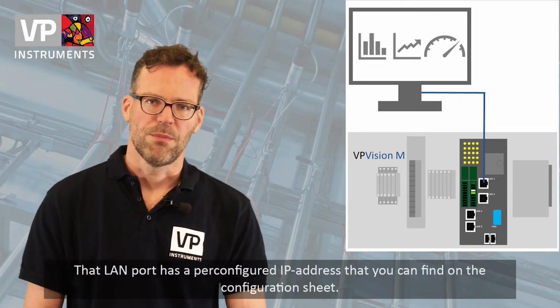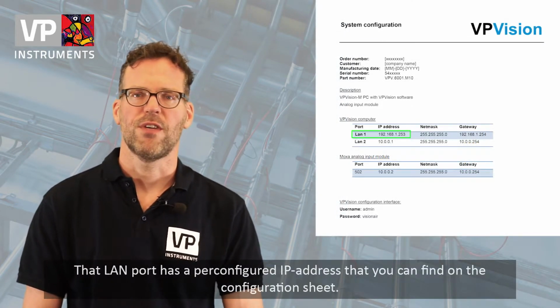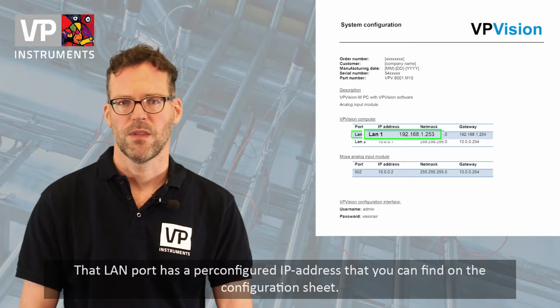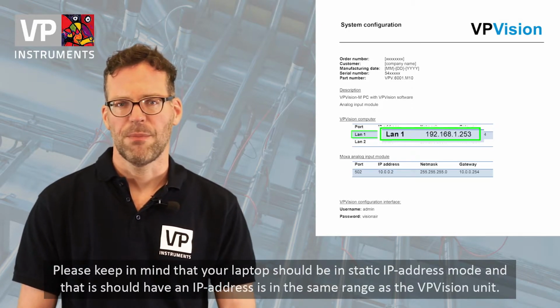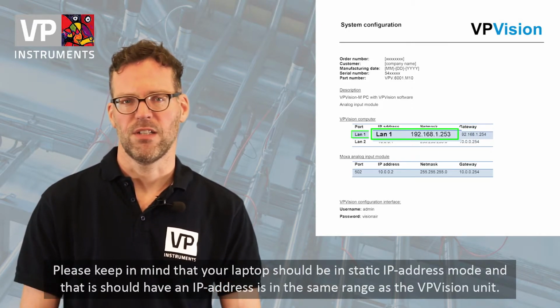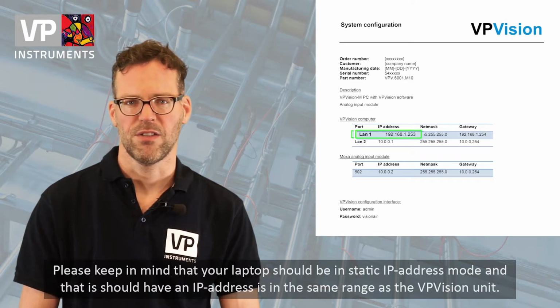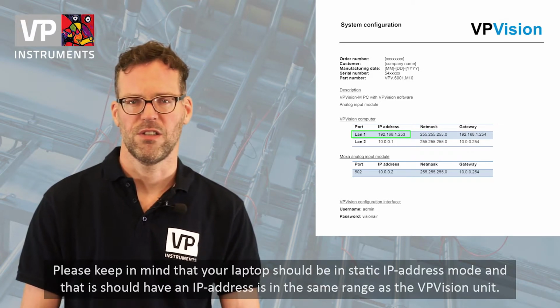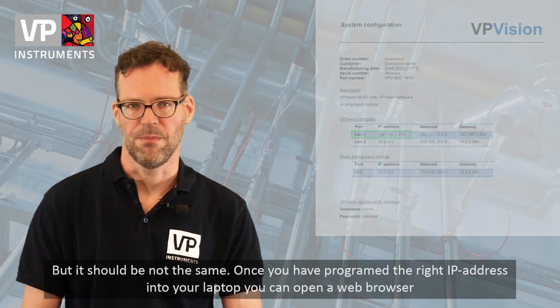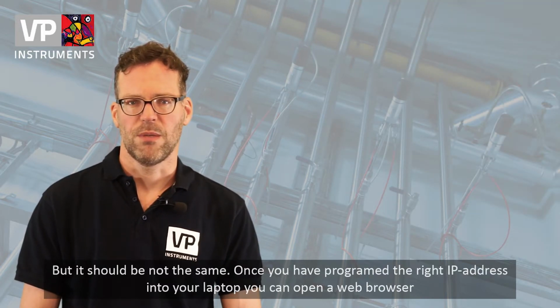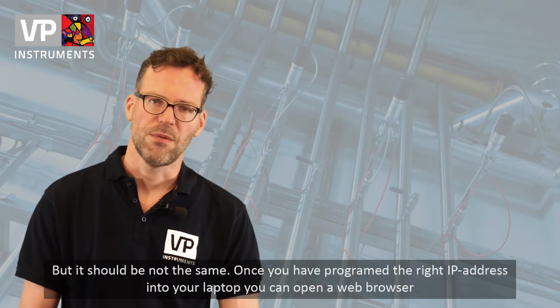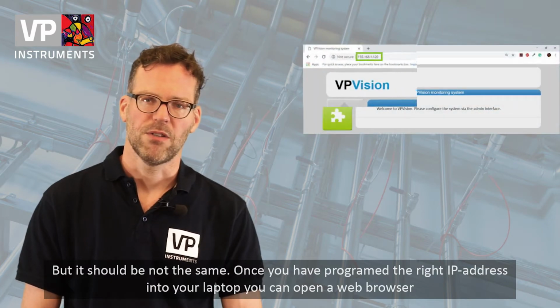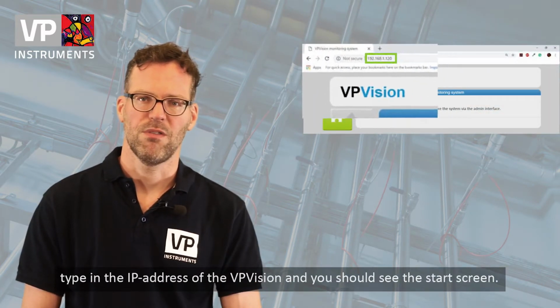That LAN port has a pre-configured IP address which you can find on the configuration sheet. Please keep in mind that your laptop has to be in static IP address mode and it should have an IP address in the same range as the VPVision unit, but it should not be the same. Once you have programmed in the right IP address into your laptop, you can open a web browser, type in the IP address of the VPVision and you should see the start screen.